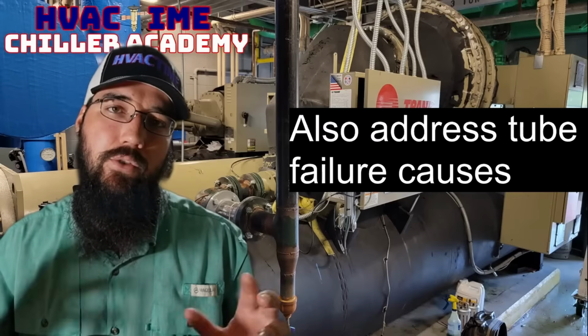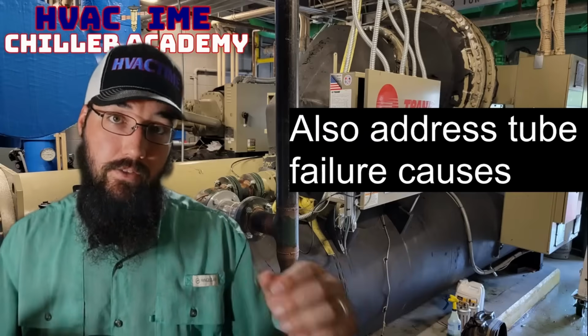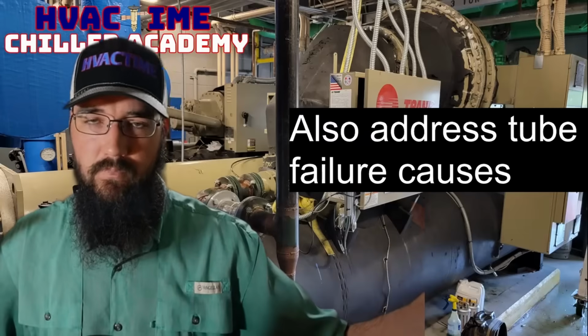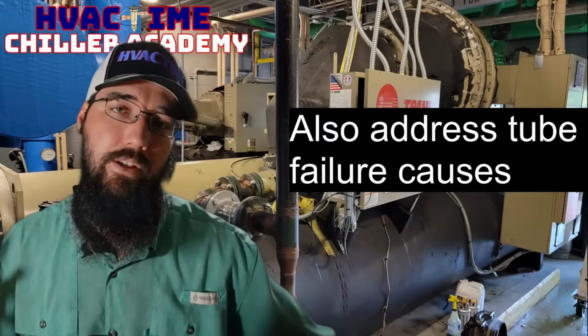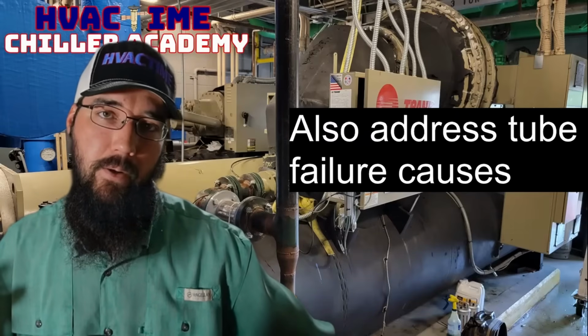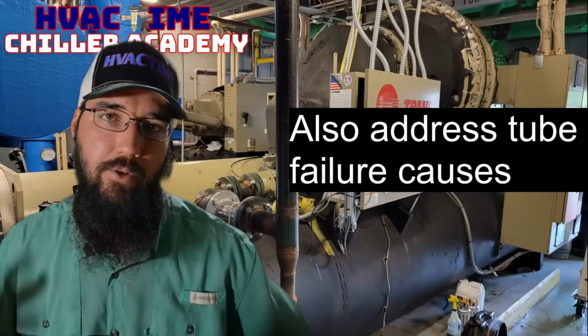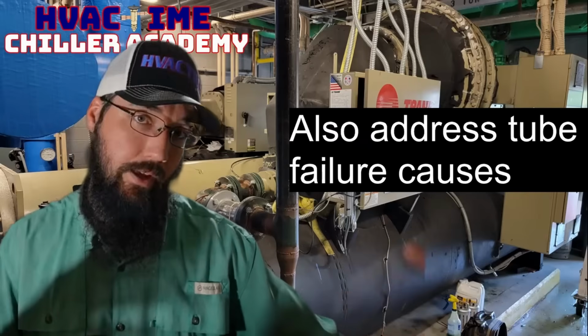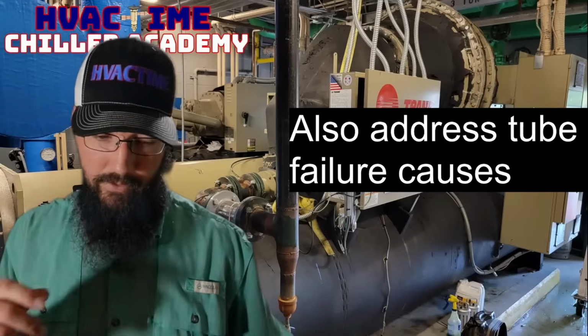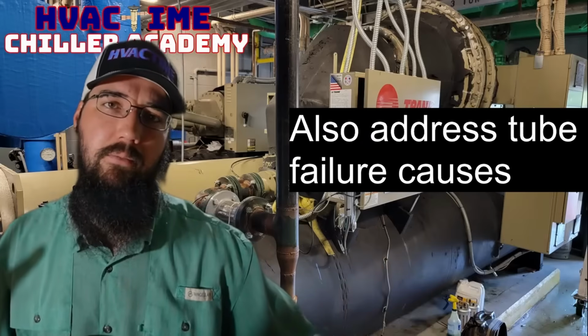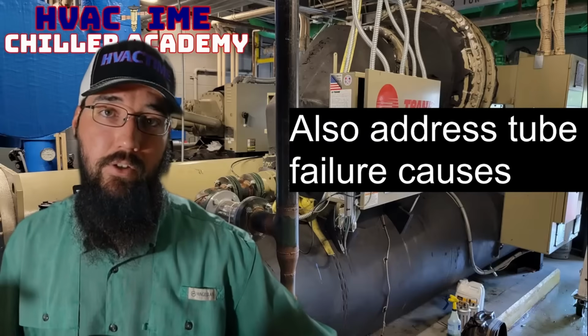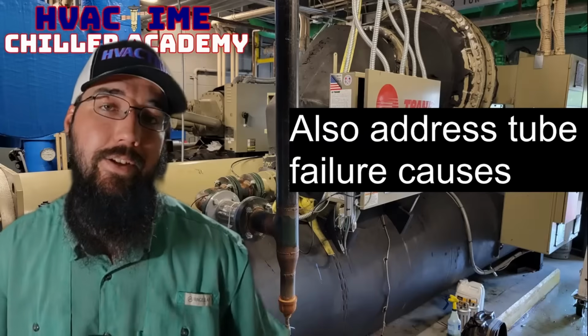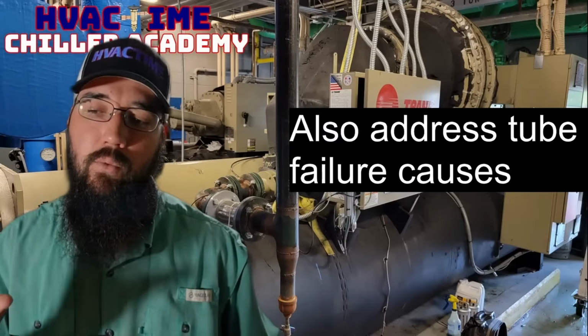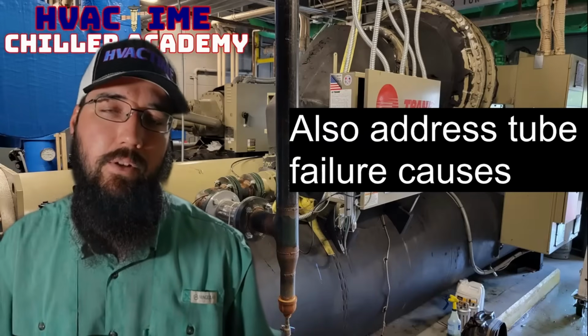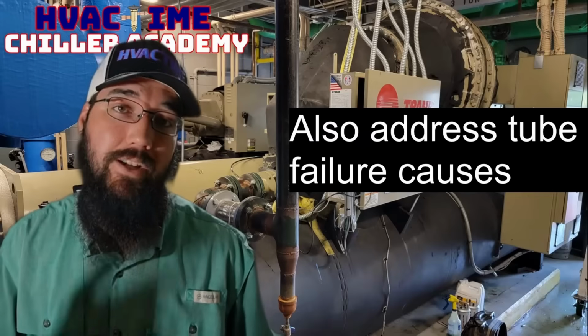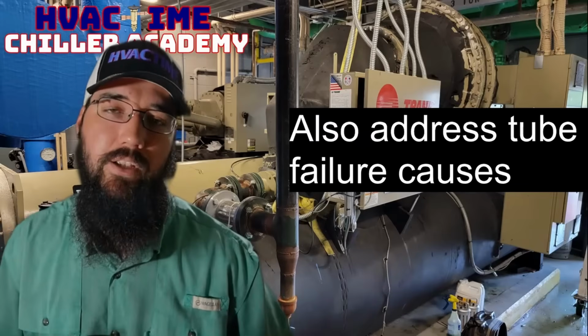In that event, you're going to plug that tube with a set of plugs. Now, to do that, you're opening up both sides of the tube sheet. Okay, so that'll depend on your piping, on how difficult that will be, whether it's a two-pass or a single pass or otherwise, but you're going to open up both ends of the tube sheet, and then that particular tube that is leaking, or let's say you had an eddy current test done and you found that you had a couple of tubes in there with a really thin wall, so they were dangerously thin, put a little bit of sealer on a plug.